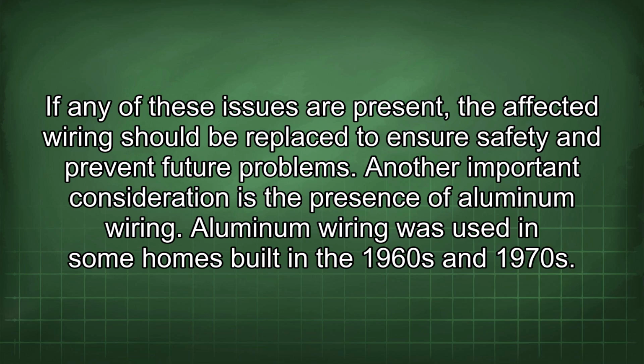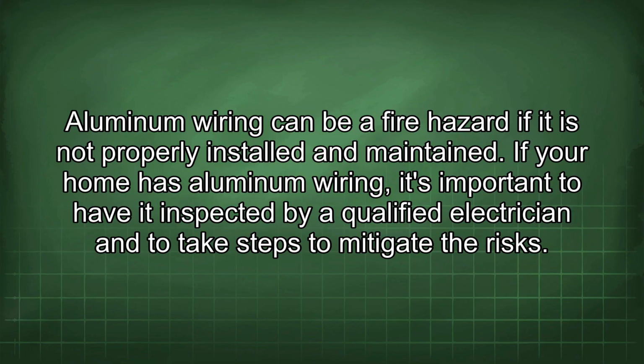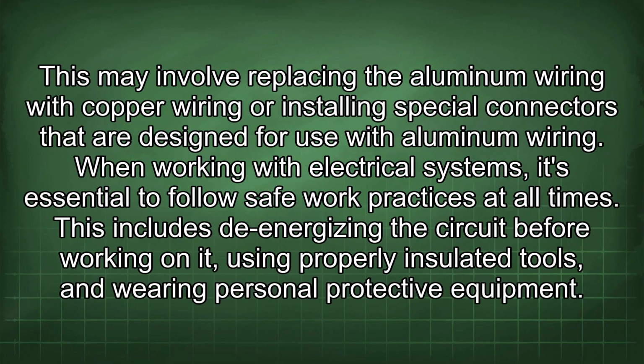Another important consideration is the presence of aluminum wiring. Aluminum wiring was used in some homes built in the 1960s and 1970s. Aluminum wiring can be a fire hazard if it is not properly installed and maintained. If your home has aluminum wiring, it's important to have it inspected by a qualified electrician and to take steps to mitigate the risks. This may involve replacing the aluminum wiring with copper wiring or installing special connectors that are designed for use with aluminum wiring.